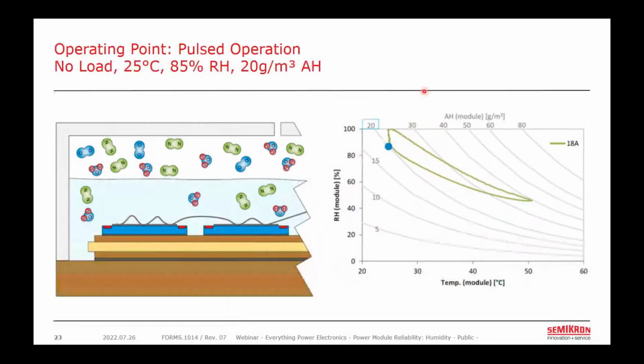So we start with a starting condition here where the power semiconductor module has been soaking in this environmental chamber without any power, and the water and air molecules have diffused inside the silicone gel. The sensors inside the silicone gel register 25 degrees Celsius and 85% relative humidity, as indicated by this blue dot here. 25 degrees C, 85% relative humidity. This is our starting point, just the blue dot.